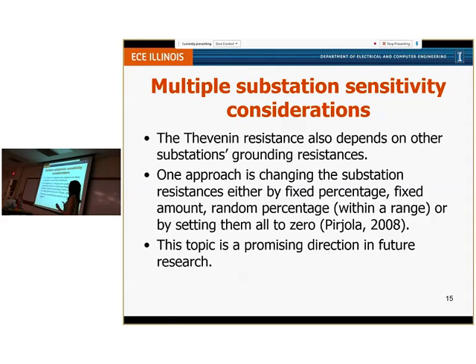And this is about our future work. The Thevenin equivalent resistance not only depends on the transmission line resistance and the transformer resistance, but also on other substations' grounding resistance, and those values we also do not know accurately. So one approach that was used by Professor Overbye in his paper published in 2008 is changing the substation grounding resistance by a fixed percentage, a fixed amount, or a random percentage in a range like 20% or 100%, or setting them to zero as in the case of perfect earthing. And hence, we are also researching in this direction.